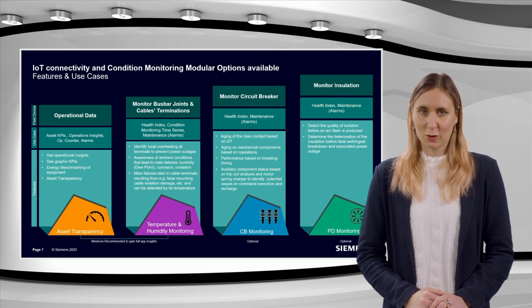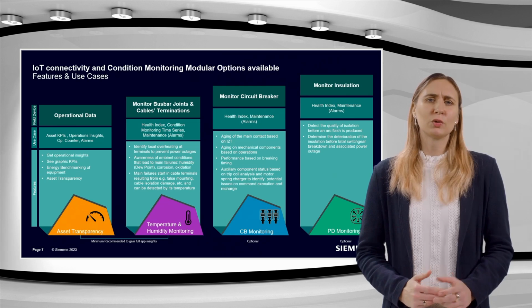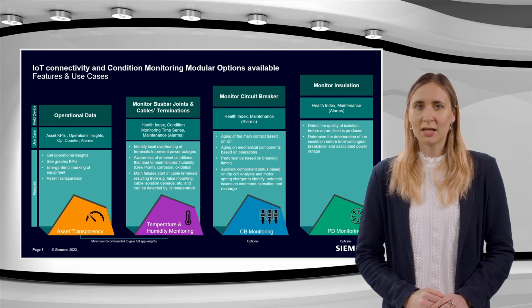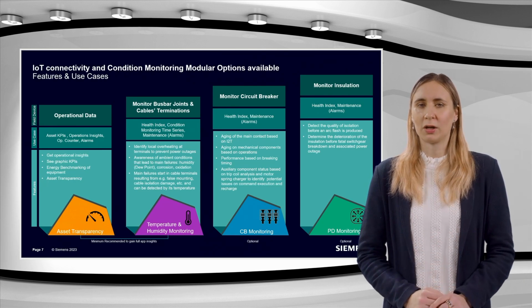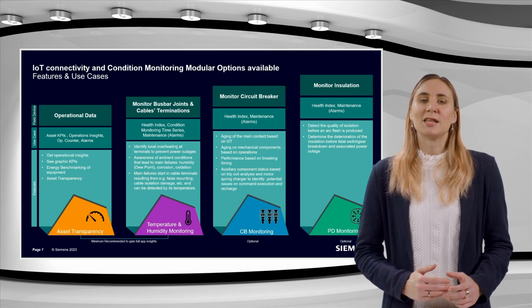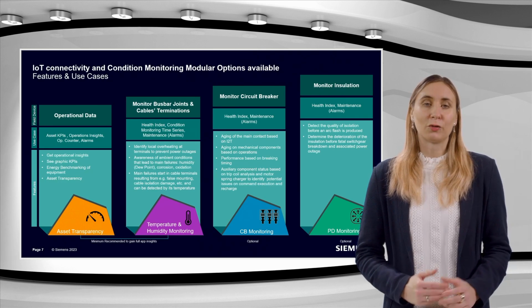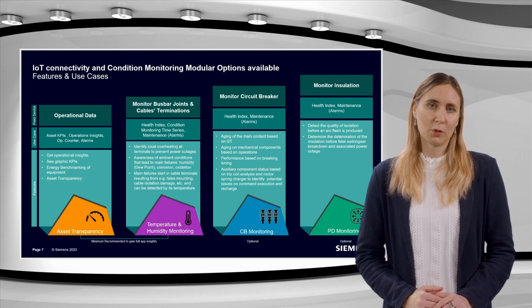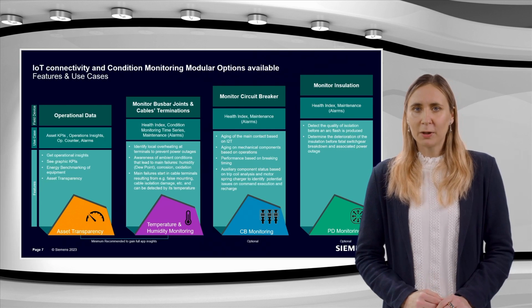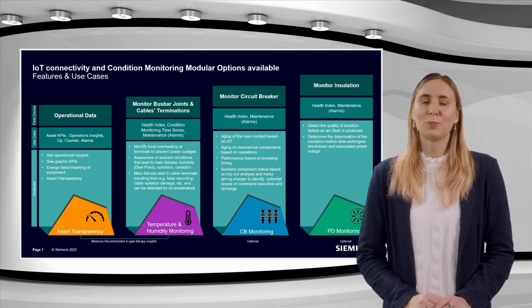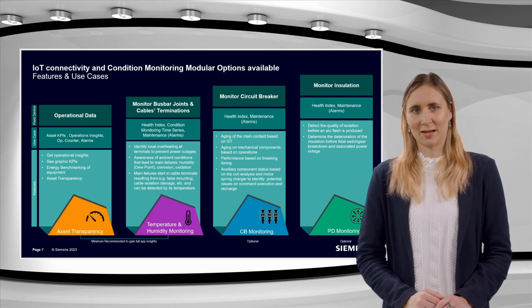Second is circuit breaker monitoring. It is usually done during scheduled shutdowns and checks whether the circuit breaker is working as expected. Circuit breaker monitoring can detect faulty circuit breaker mechanisms and components, for example the tripping coils, the closing coils, the spring-loaded drive motors, and the switching time.